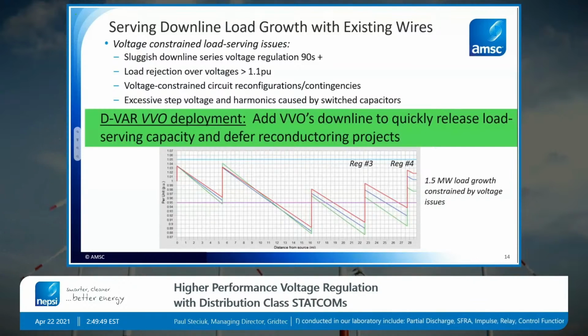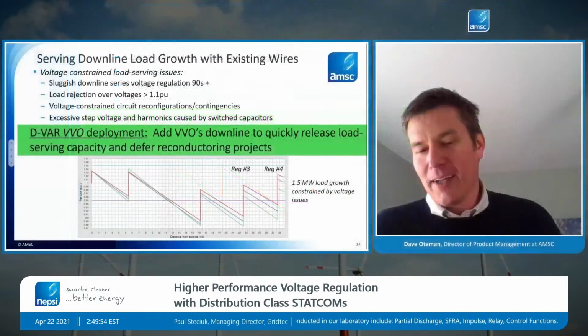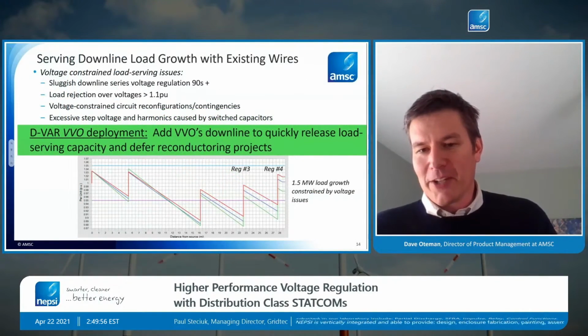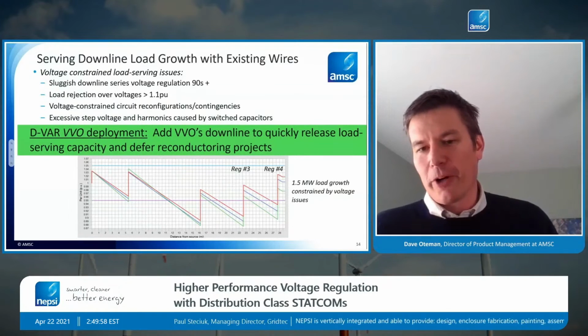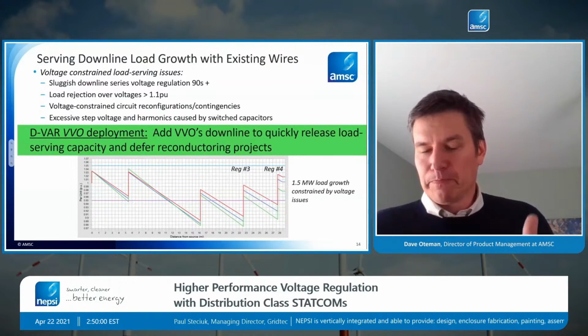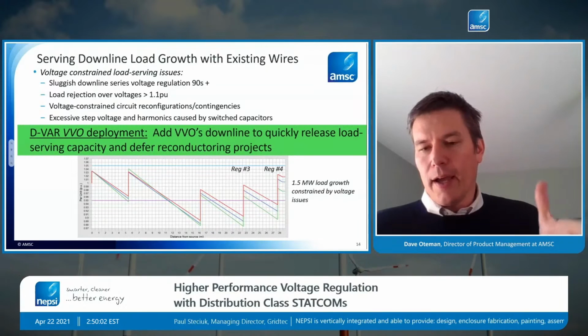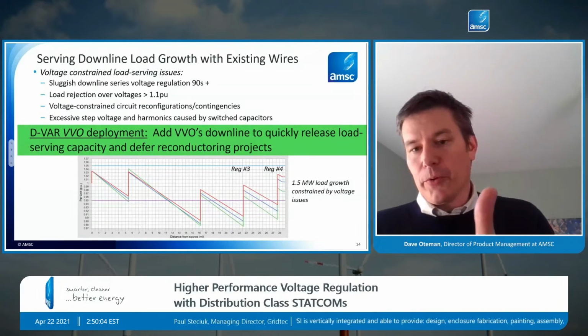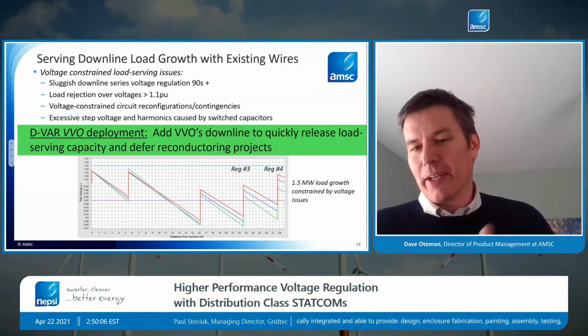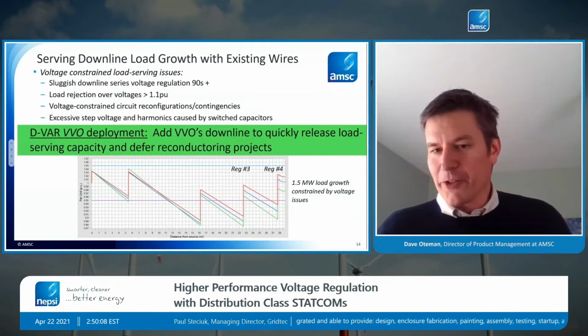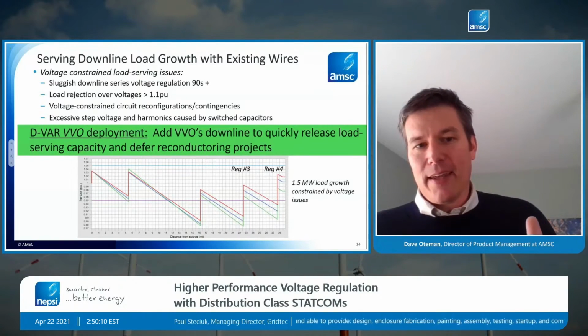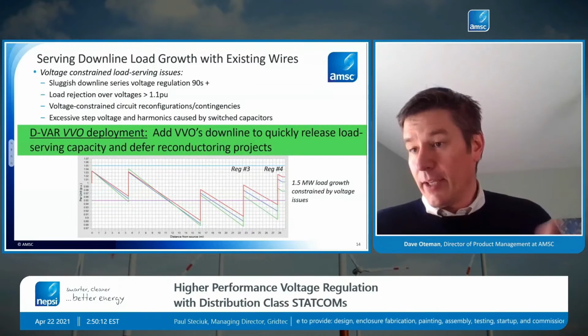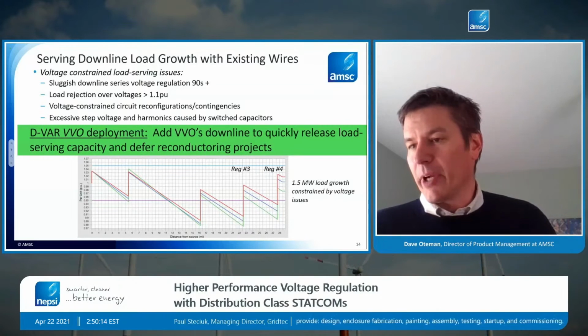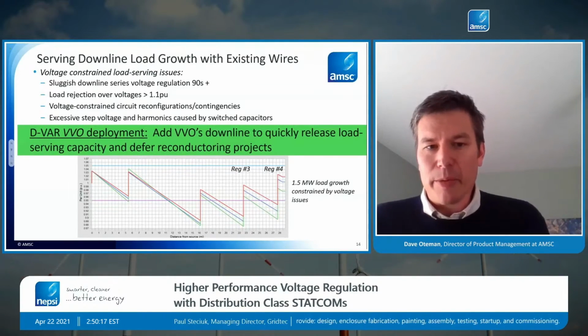So STATCOMs can actually be used as the primary voltage regulator on these longer downline locations. We're showing Reg 3, Reg 4 here. On this circuit, the VVO is able to replace those 2 downline regulators and be the primary voltage regulator and address these voltage constrained issues that a typical series regulating device is not going to be able to address.